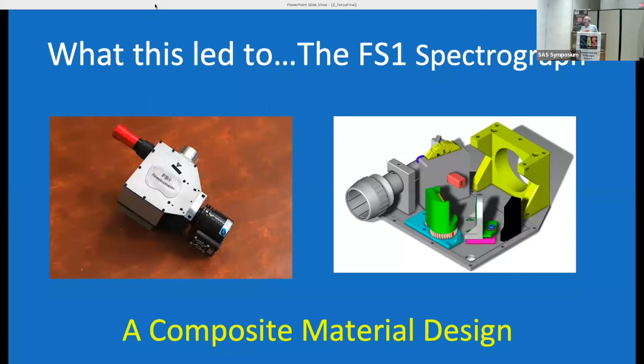Okay, top of the list in that gripe session was focusing. Every spectroscopist has had a problem with focusing, some of us nightly, and it comes from two areas. Firstly, there's thermal expansion that causes loss of focus. And when I'm talking about focus, I'm talking about focus on the slit, not telescope focus. And also, we are projecting a curved image onto a flat surface, which is why you get fishtails. So even focusing is a compromise, even if you get it right. So we thought we'd address that. So what did we do?